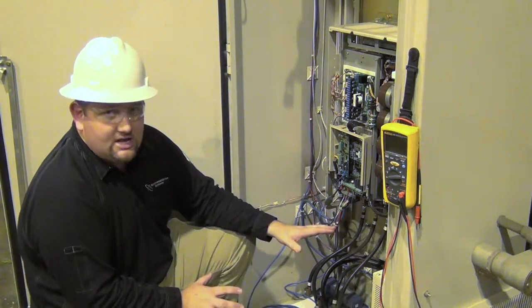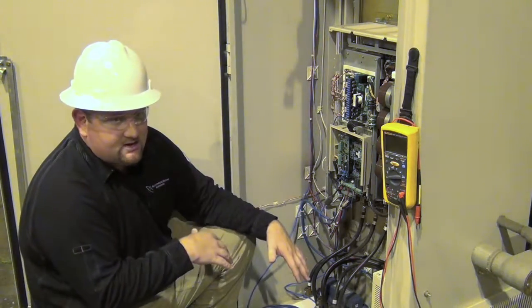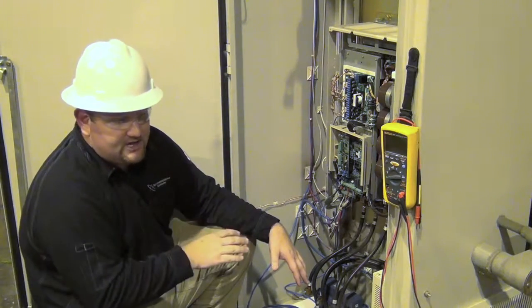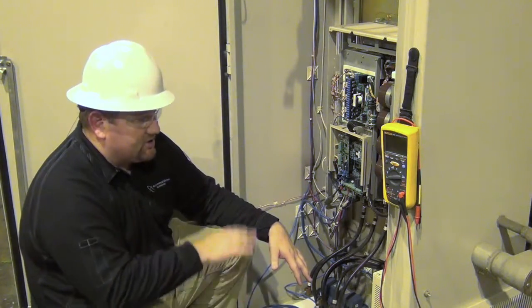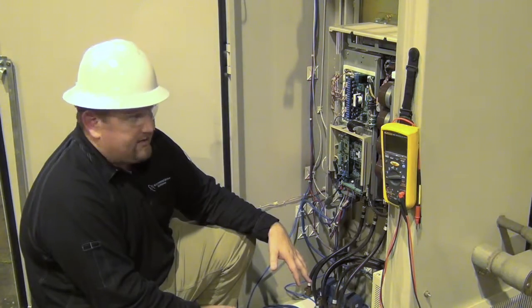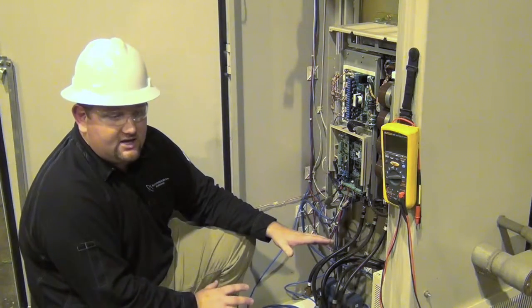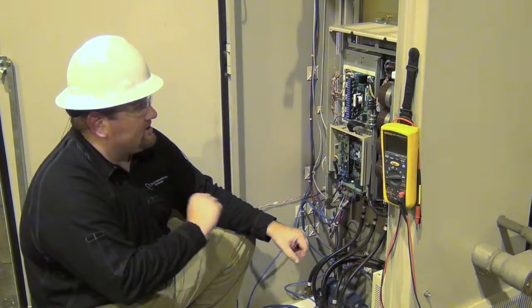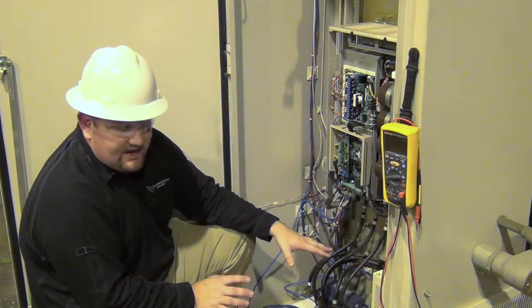So again, what I'm going to do now is I'm just going to start with the air compressor, start at the top of the drive, lightly blow it out, get as much of the dirt moving downward as I can, and then anything that's still left, I'll take our ESD vacuum cleaner to, and try and get as much of the dust and dirt out of this drive as you possibly can.